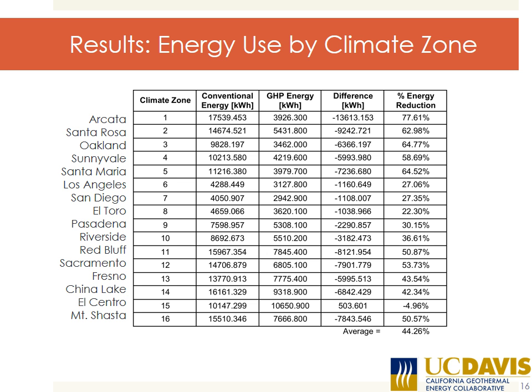They're getting high, and there are a variety of things being done for that. One is the energy required to power the compressors is dropping because the compression systems are becoming much more efficient. Another thing that's important, and it's not often figured into a COP, but it does have a big effect on the overall energy consumption of these systems, is how much energy is required to pump the fluid through the loop that goes into the ground. Those pumping systems are becoming much more efficient, and that's one place where important contributions can continue to be made.